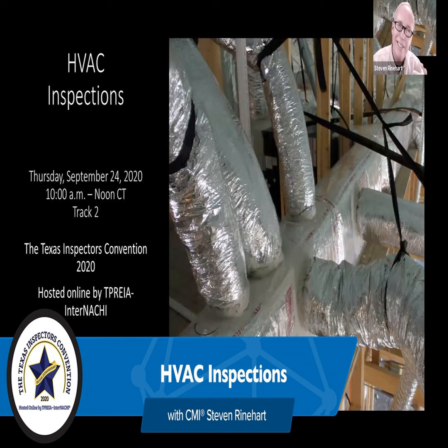Is it blowing anywhere? Before I start, I'll actually look in the traditional draft one you saw there earlier with a flashlight and look down the burners and see if there's a lot of rust residue. If it's piled all the way up, half full, I'm going to say something. If it's got much debris in there at all, I'm going to say something. Two things come to mind. Where is it coming from? They make them real thick because they know they're going to rust, kind of like cast iron drain pipe. They know it's going to rust. They make it thick so it lasts longer.